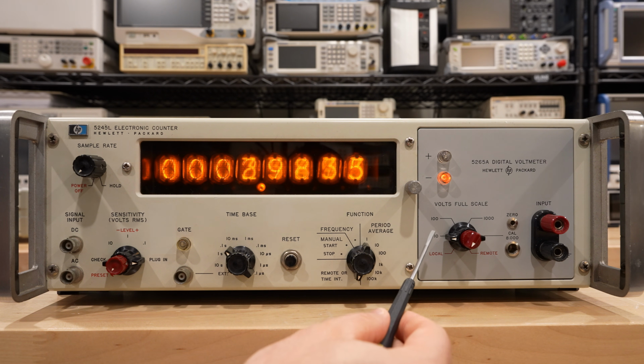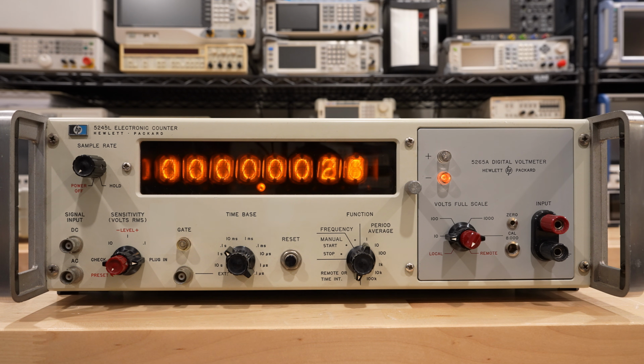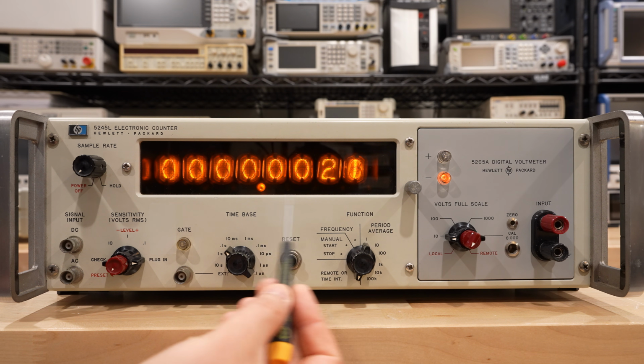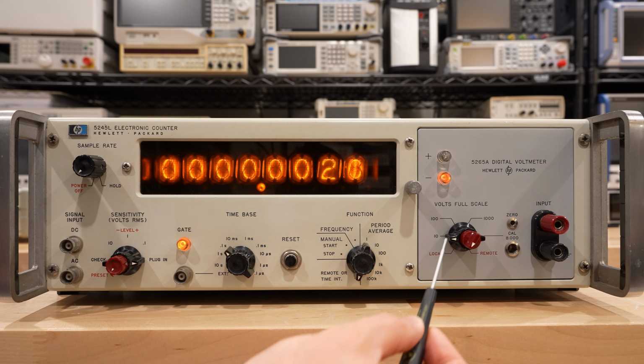You can see that this is set to a 10 volt scale, which is the lowest scale we have available. And let's wait for it to stabilize a little bit, as well as of course come up to temperature before we do any zeroing or any calibration. Okay, we have warmed up a little bit and everything is now stable. Now we should try and zero the instrument. You can see that we are indeed reading a little bit of an offset over here. Remember, we're on a 10 volt scale, which is the smallest, and we are reading 0.0021 volts or so, which is actually not that large.